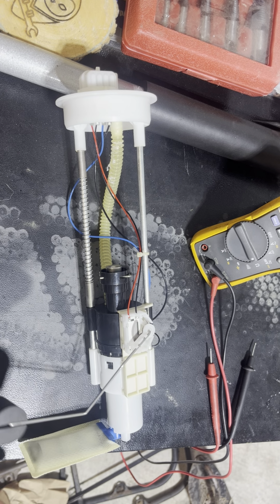Like if you gotta do some troubleshooting, for example, first thing for sure, check your fuel pressure using a pressure gauge. And it has to be a tight connection, you gotta have the right fittings and everything. That will tell you if your pump is working and if your regulator is good.